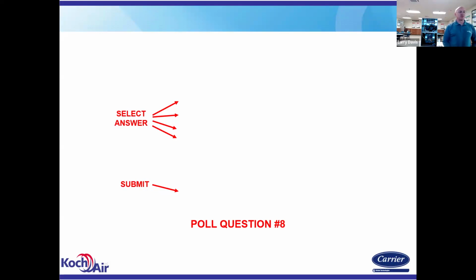The question is, does a furnace board save any of the IntelliSense information that can be accessed through NFC? No, it does not. You will get from the NFC the same, the only information, you won't get the temperatures. That's really the only difference. And the motor blower speed, but you'll get your fault history. You'll get the fault count, operation. That's information you'll get through NFC that you won't necessarily get through IntelliSense.